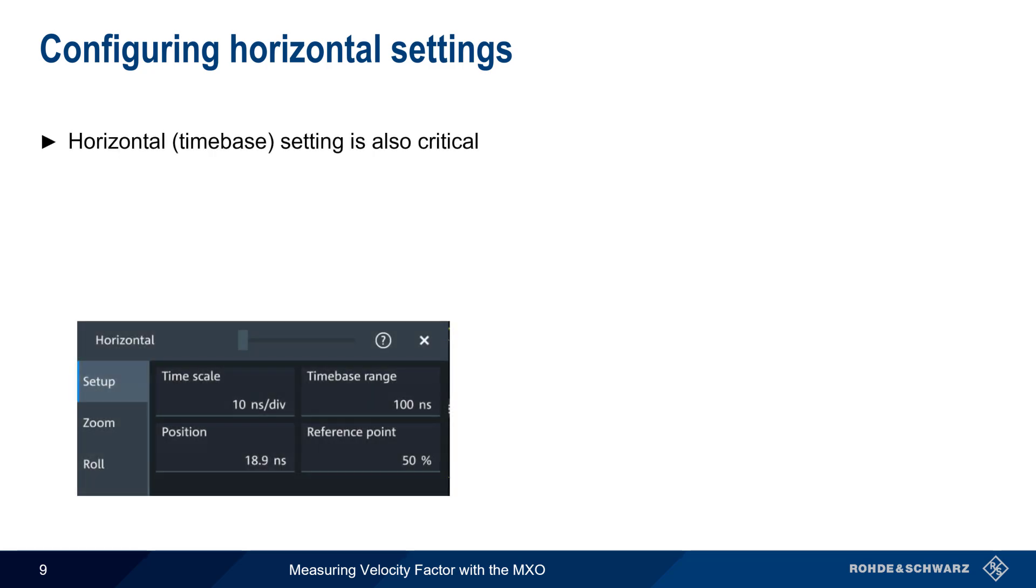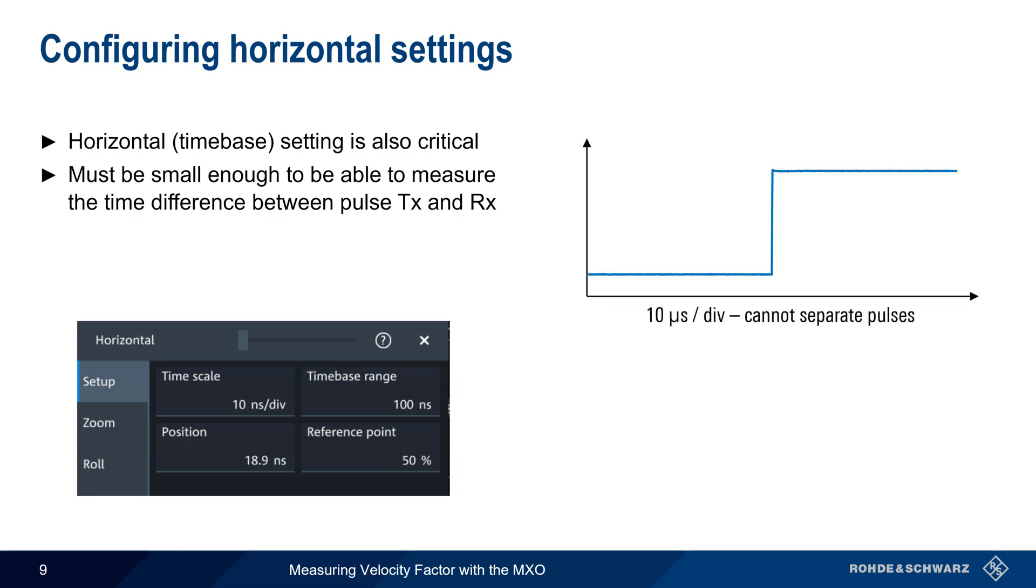The horizontal or time base setting, that is seconds per division, is also crucial when measuring velocity factor. The time base must be set small enough to measure the time between when the pulse was transmitted and when the reflected pulse was received. If the time base is set too large, as shown in this example, it may be impossible to visually separate the transmit and receive pulse.